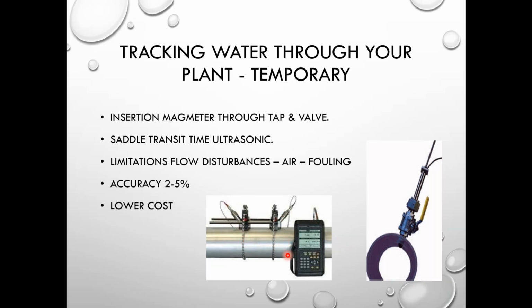Limitations to these types of meters, of course, is, if you've got solids in there, they can foul the transit time with ultrasonic sensors. If you've got concrete, steel type pipes, sometimes it has a harder time traveling or sending a signal through that, as well as air. If you've got air in the line, it could affect you. But these are good low-cost ways of going out and trying to do verifications on your flow meters at the facility.